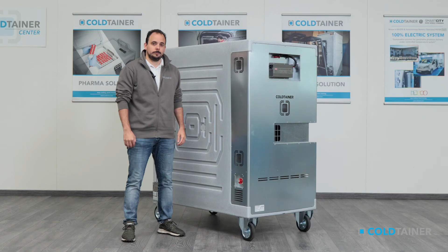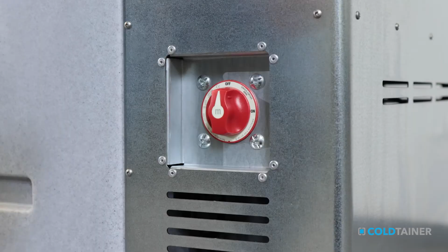Now I will show you how to use the Coldtainer. The first thing to do is to put the main switch, the red button found on the right side of the Coldtainer, into the on position, like this. The second thing to do is turn on the switch found on the front side of the Coldtainer, next to the display, under its protection cover. Then you have to wait until you see the temperature detected by the internal probe.